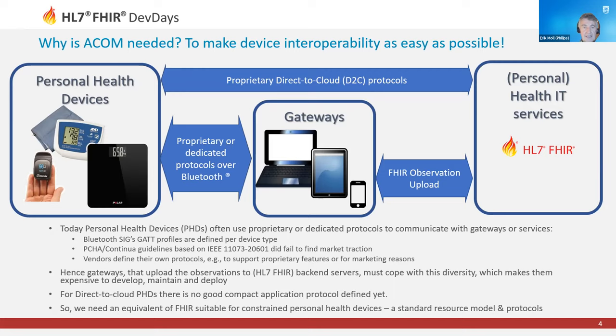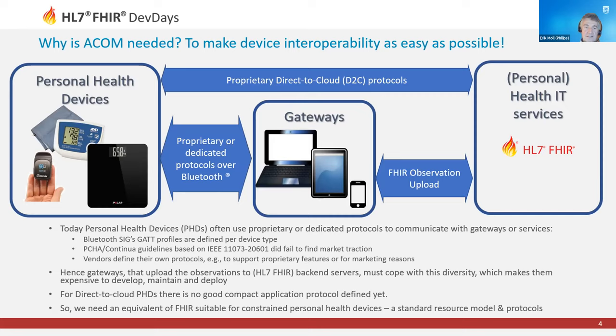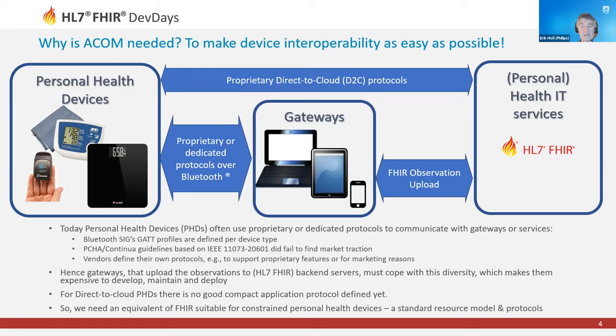There was an alternative, the classic IEEE 11073-20601 standard, the optimized exchange protocol for such devices. But that failed to find market traction because of lack of support in common platforms and its complexity. As a result, we see vendors defining their own protocols or taking a GATT profile from the SIG and adding features to it, making it not interoperable. The consequence is that gateways that need to deal with such devices must cope with a lot of diversity, making them expensive to develop, maintain, and deploy. For this context, we do need something that is universally applicable, easy to implement, and compatible with what's desired on the right side in the healthcare IT systems. Something like FHIR, but suitable for binary constrained protocols. That's why we started the ACOM-related work.